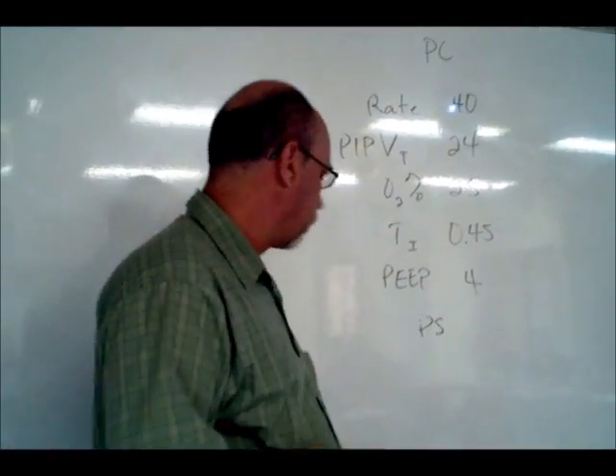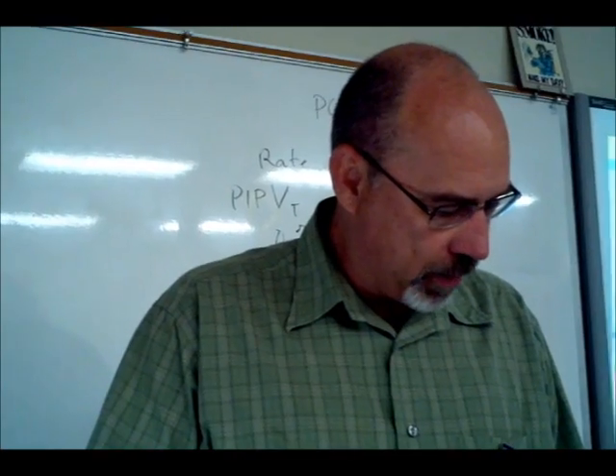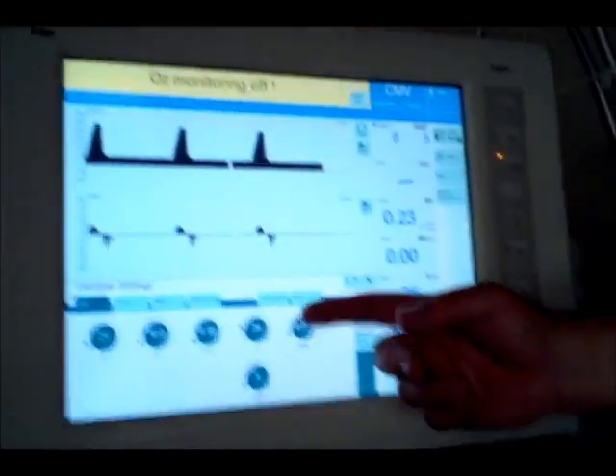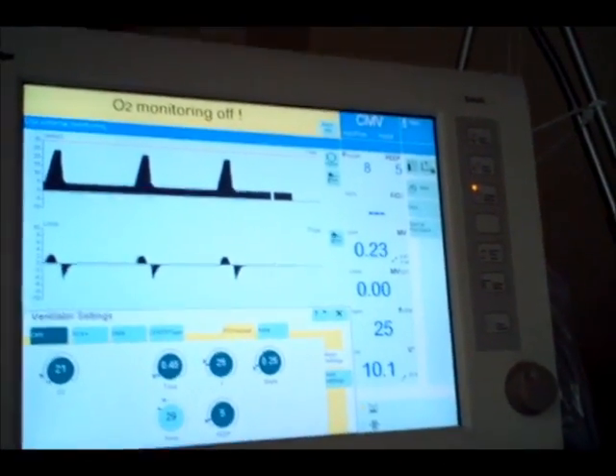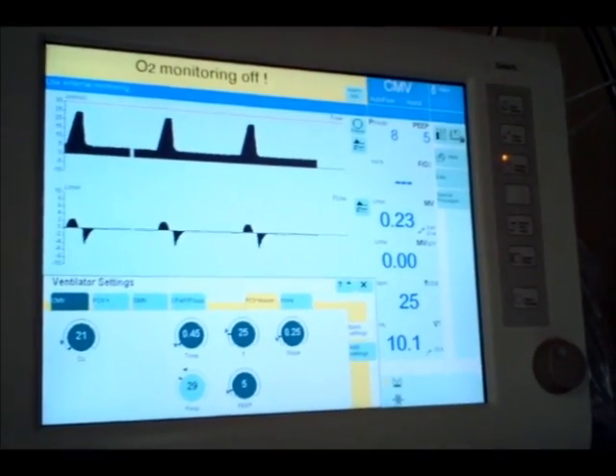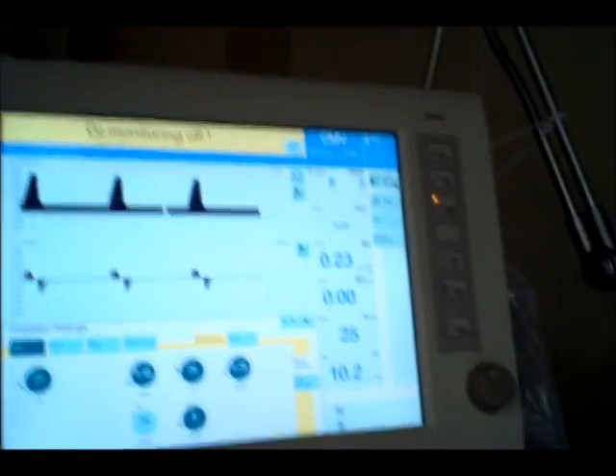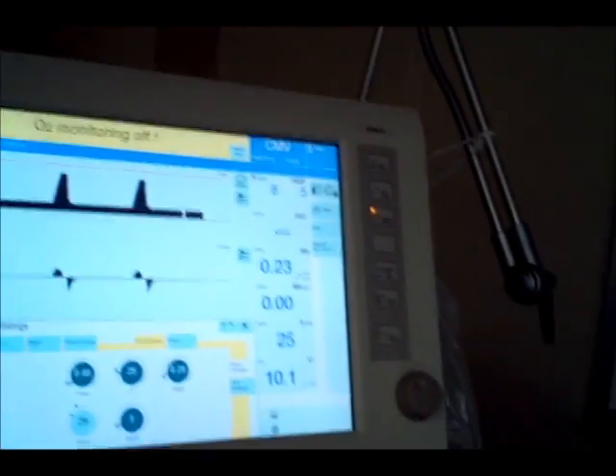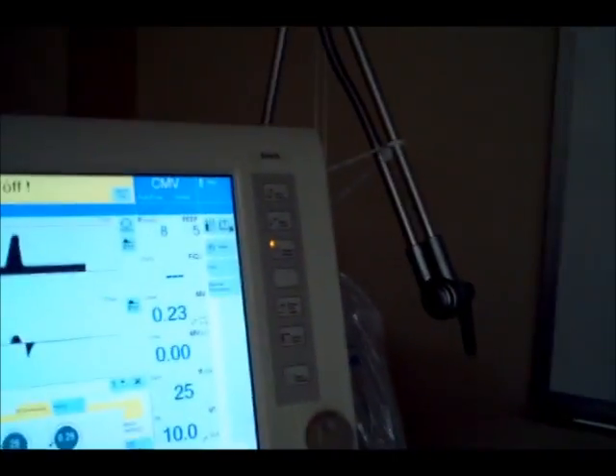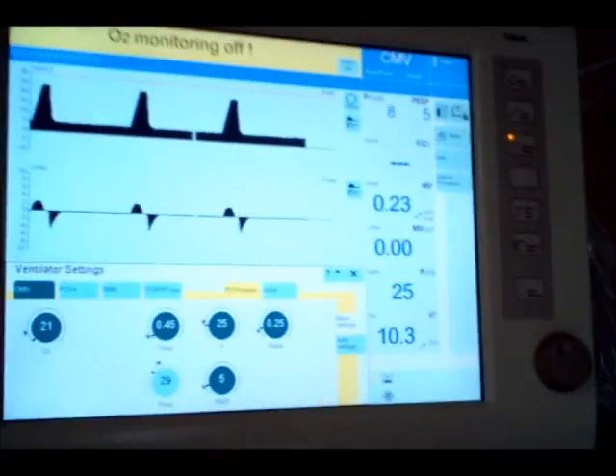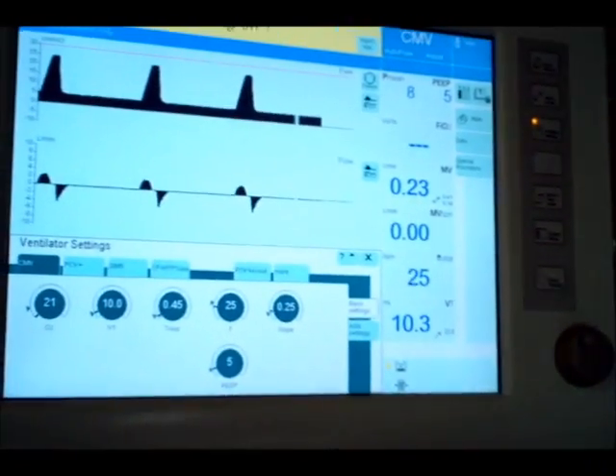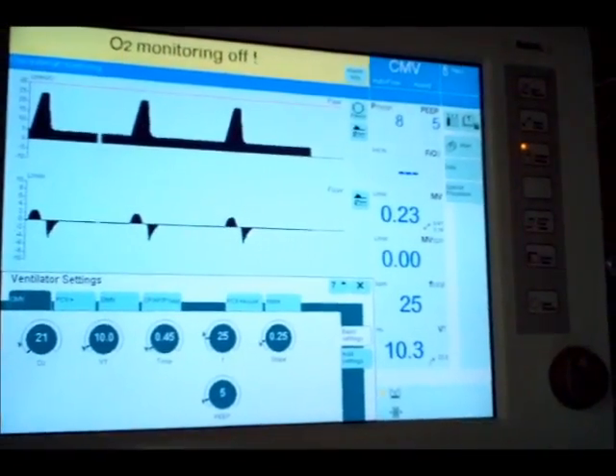All right. Now this is the tricky part, and we're on section 9 of your checkoff. So under letter A there it says change to PCV plus assist mode. Okay, because there's a PCV plus and there's a PCV plus assist. So we want this one. If you get stuck and you can't remember which is which, PCV plus assist is where you set a PIP, but there is no pressure support level there. So now we want the one without pressure support.